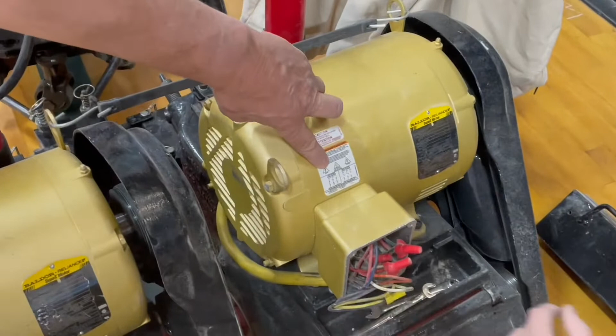This isn't strictly necessary, but it helps to keep track of which your hot lines are. We're making a note on our cover plate that for low voltage, the 2 and 8 line is connected to white, the 1 and 7 to black, and the 3 and 9 to red. So coming back to our plate, the hot lines are connected to 2 and 8, 1 and 7, and 3 and 9. We're keeping track of them.